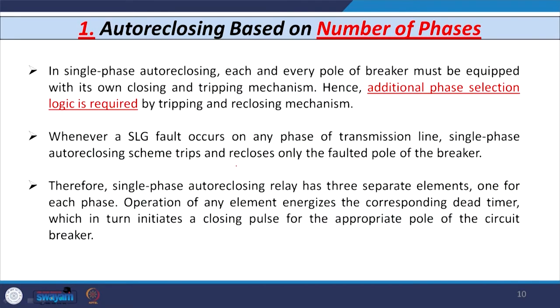For single phase auto reclosing, each pole of the breaker must be equipped with its own closing and tripping mechanism. Additional phase selection logic is required for tripping and closing in case of circuit breakers. Whenever a single line-to-ground fault occurs on any phase of the transmission line, the single phase auto reclosing system trips and restores only the faulted phase of the breaker.